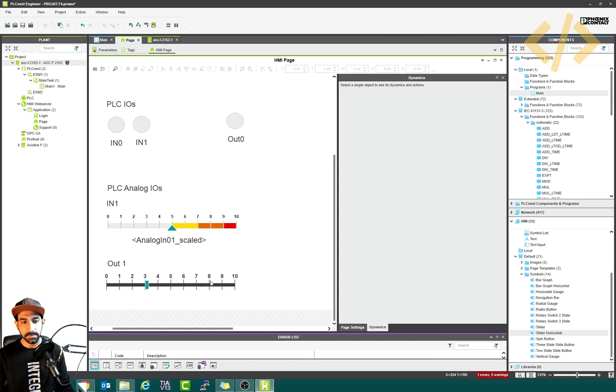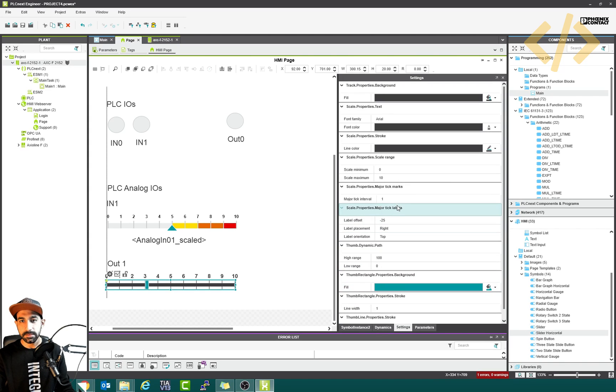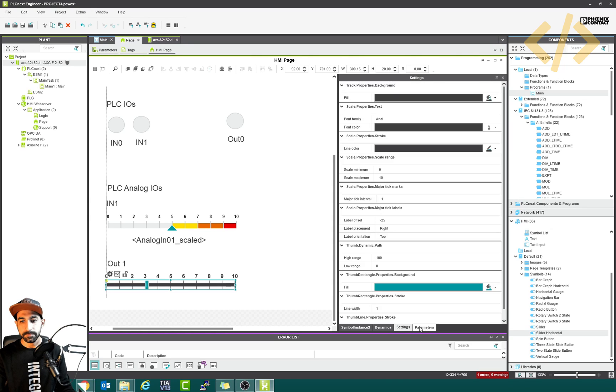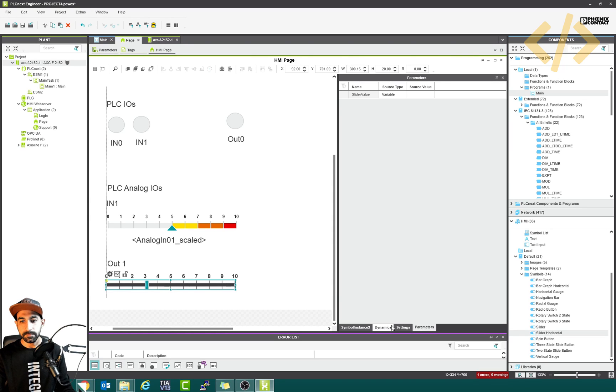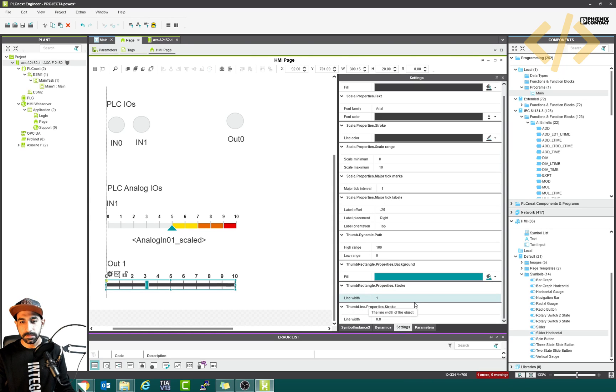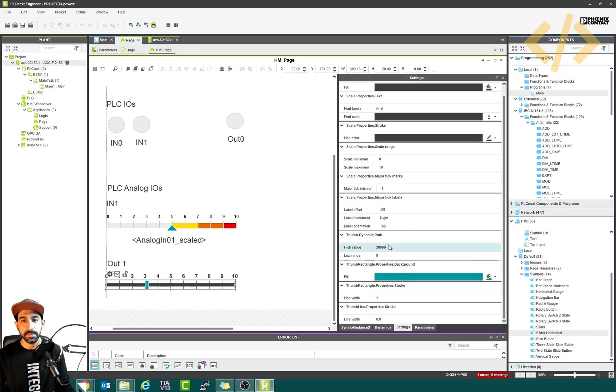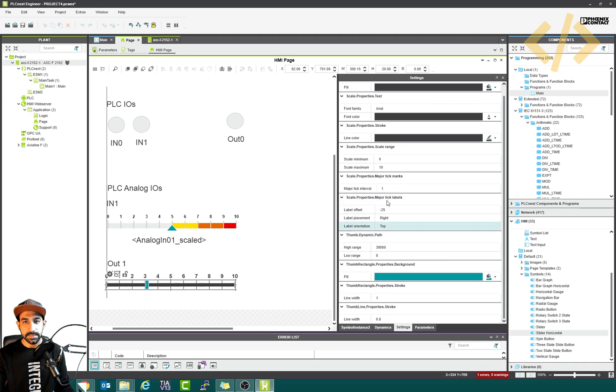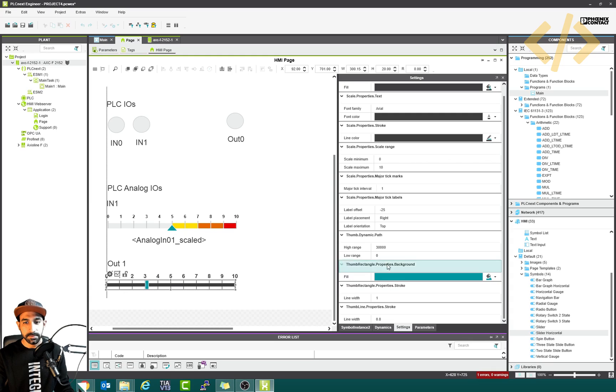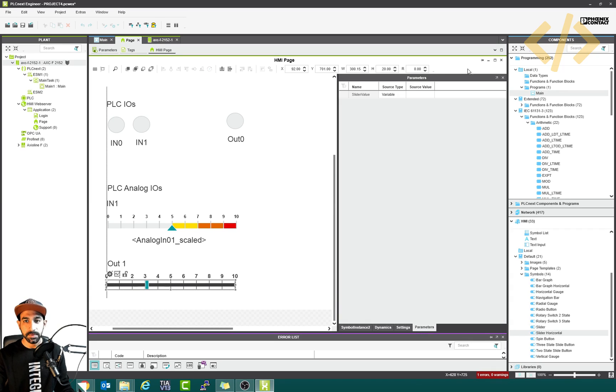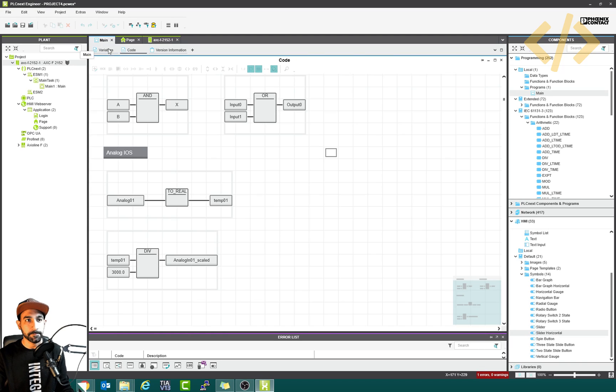And similar to analog input, we will also change its dynamic scale. Where is that, should be in the settings, thumb dynamic path. So high range will be 30,000 again. So now our settings are defined zero to 10 volts, scaling of zero to 30,000, and parameters and the variable. So let's come to the variable after we do some changes in the PLC programming.